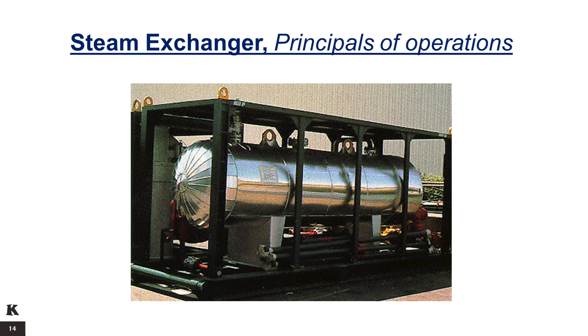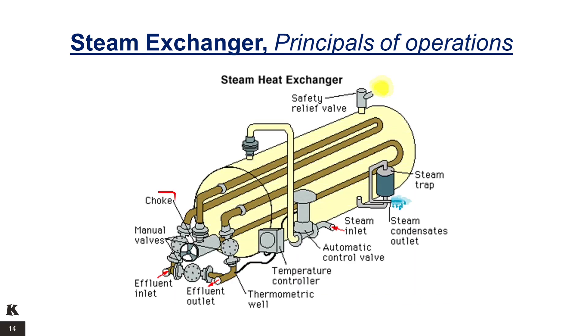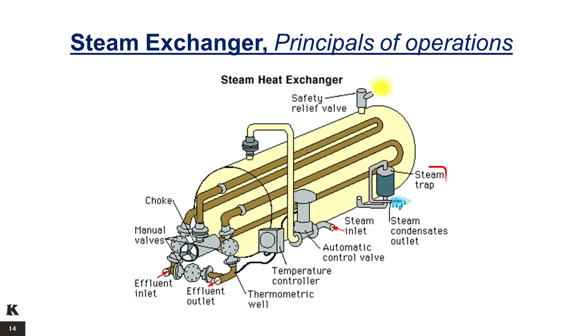Steam exchanger — Principles of Operation. The unit is skid-mounted with a protective frame and consists of a steam vessel containing two coils through which the fluid passes. A choke assembly enables the well to be controlled at the heater rather than the choke manifold after the well fluid has passed through the first coil section. An inlet manifold of three gate valves controls fluid flow and provides a bypass of coils and choke. The steam flow into the vessel is regulated by an automatic control valve on the steam inlet to maintain a preset effluent outlet temperature. There is a steam trap on the steam outlet line. The steam vessel is protected by a safety valve with a flange available for either an additional safety valve or a 6-inch bursting head. The steam vessel is insulated with glass wool and is covered with an aluminum jacket.